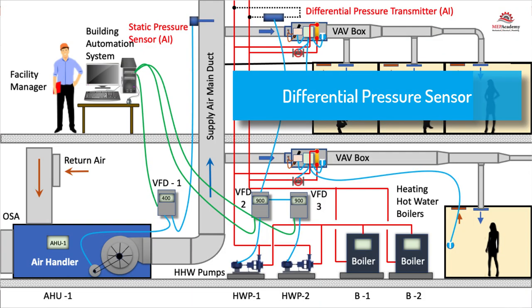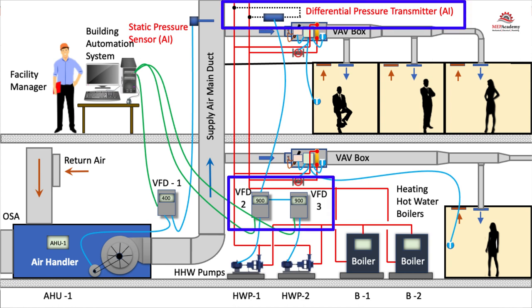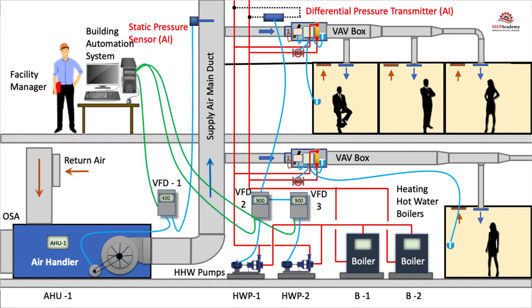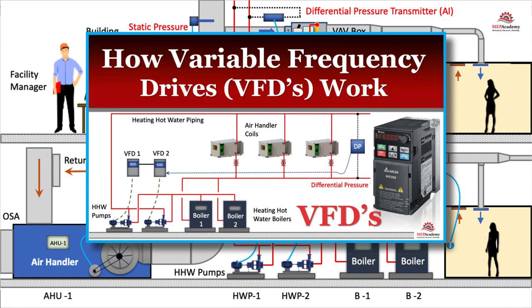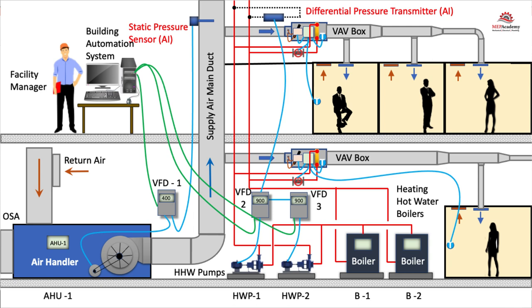Differential pressure sensor. Differential pressure sensors, in combination with variable frequency drives (VFDs), can be used to control the speed of pumps in a system. Differential pressure sensors are installed in the system to measure the pressure difference between two points, typically just before the most remote coil in the system. The sensor measures the difference in pressure across a flow element such as an orifice plate or a flow sensor. The differential pressure sensor provides a feedback signal to the control system indicating the actual pressure differential. A desired target differential pressure set point is established based on the system requirements and design parameters. The control logic compares the actual differential pressure feedback signal with the set point.